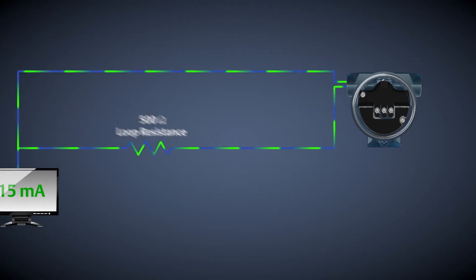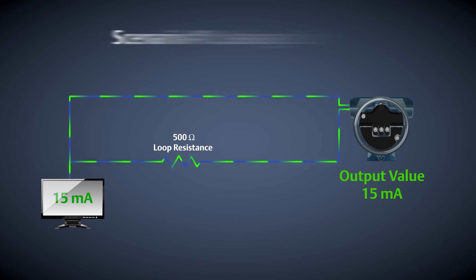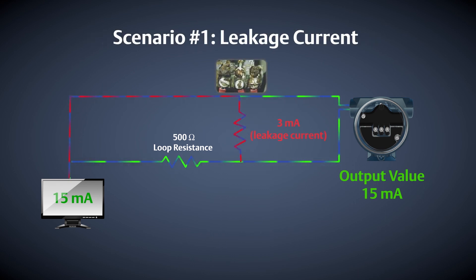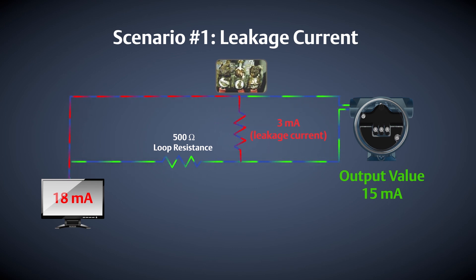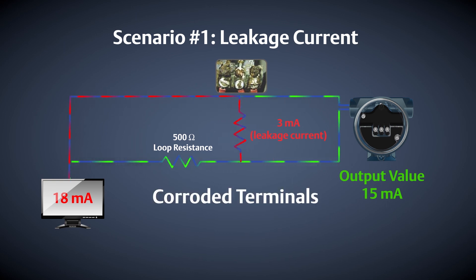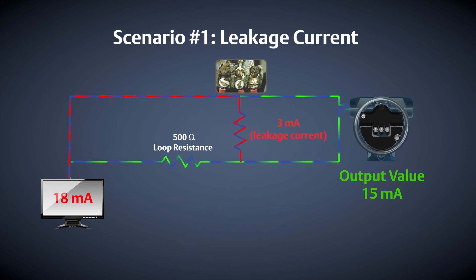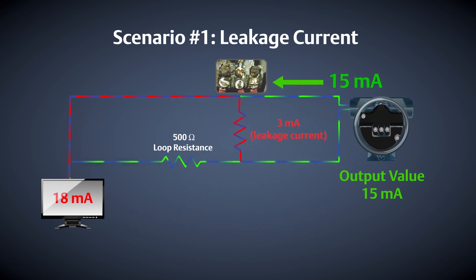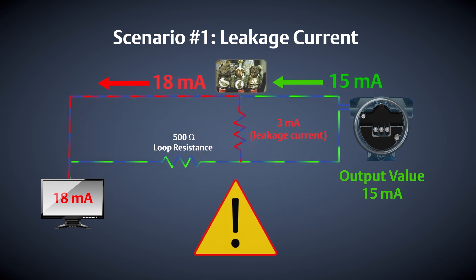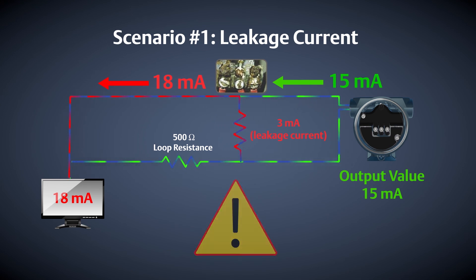Let's picture two scenarios which can lead to on-scale failures. The first scenario is a circuit that has leakage current, which is an electrical issue where an additional current path is created in the wiring. Leakage current can be caused by a number of human or environmental factors, including corroded terminals, water in housings or conduits, shorted wires, and others. This additional electrical path causes a discrepancy between what the transmitter is outputting and what the control system is receiving, resulting in an on-scale failure condition where you could be taking control action on bad information.